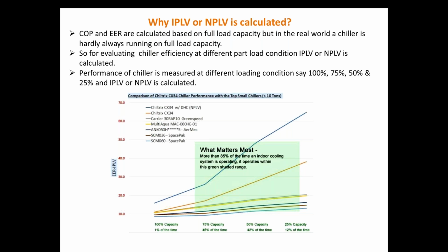So for that, the term IPLV or NPLV was coined in order to take into account the part load performance of your system. Chillers, in this case I am referring to, supply chilled water. Clear? So these chillers are the refrigeration system in short.